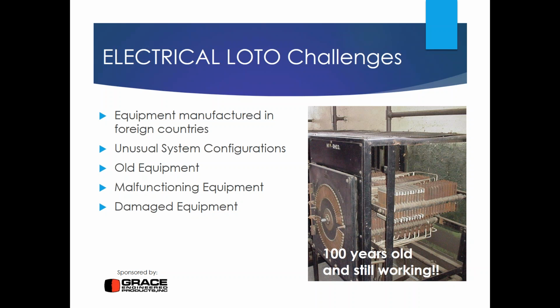Some equipment will be damaged to the point where it would be unsafe to use it for isolation of circuitry. One good example of this is that molded case and insulated case circuit breakers are actually rated for only a single close into a short circuit. So if you reset a breaker into a dead short, you've actually used up the design life of that breaker, and it would not be a recommended procedure to use it again until that device has been tested and recertified or rebuilt. With that said, that's one of the more common things that happens in industry. Trial closes are common. They stress the electrical system, and they are beyond the design life of the breaker itself.